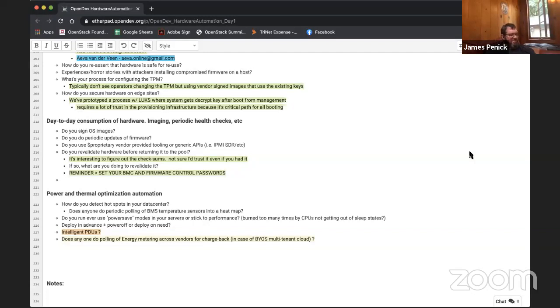Something I'd done in the past, I mean, it's so long ago, is written in Perl. I wrote something that was going through one of our smaller data centers, and it was querying all the smart PDUs and just asking them what their temperature sensors saw. And then it was taking that information and putting it into a database, which also meant it captured the power draw from the PDU, which was useful as well, because we could detect which PDUs were overloaded. And if you've ever had to go and install loose gear in a data center, it gets to the point where you're doing the math and calculating how many watts are actually being used in a given rack, to see if you can sneak another machine in.